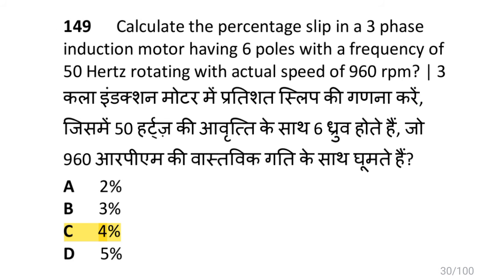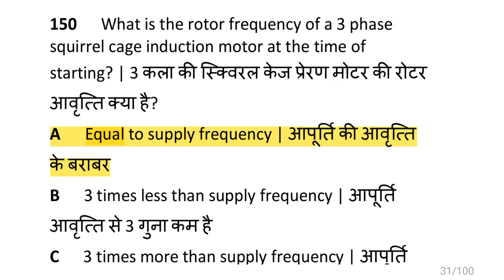Calculate the percentage slip in a three phase induction motor having six poles at 50 Hz rotating at an actual speed of 960 RPM. Using the formula: (Ns minus Nr) divided by Ns, multiplied by 100, with synchronous speed 1000 and rotor speed 960, the percentage slip is 4%.